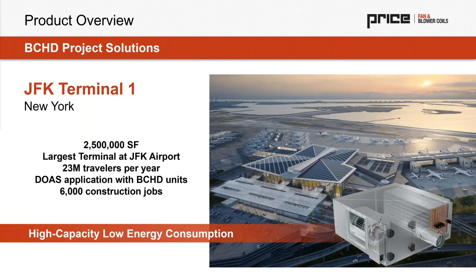Some other key projects for these blower coils: JFK Terminal 1 in New York is utilizing our new blower coil due to its capabilities to integrate very well with the DOAS application. The interesting thing with this one in particular was the custom enclosures and wiring for components that we saw for this project. So multiple hydronic valves, differential pressure transducers for accurate low flow outdoor air measurement and demand controlled ventilation, discharge air temperature probes, carbon dioxide sensors, the whole gamut, all installed and shipped as a single assembly to site.